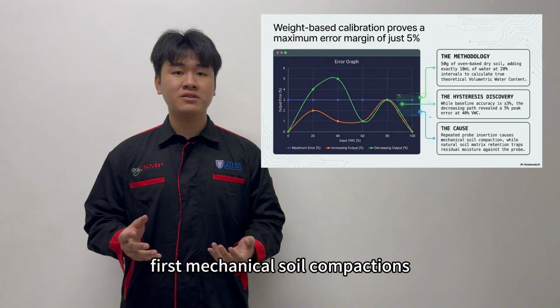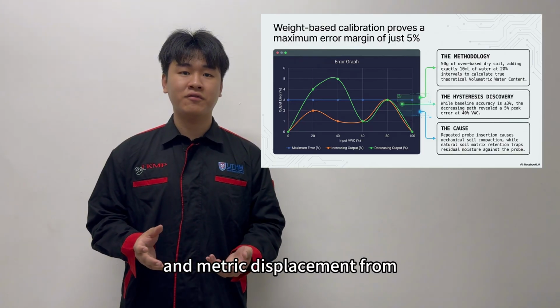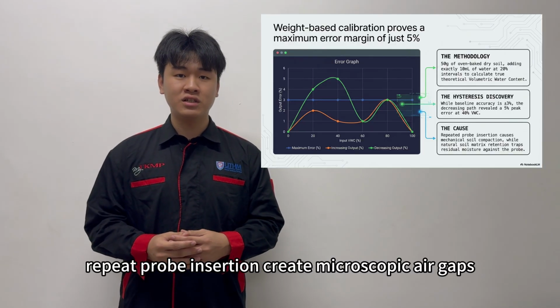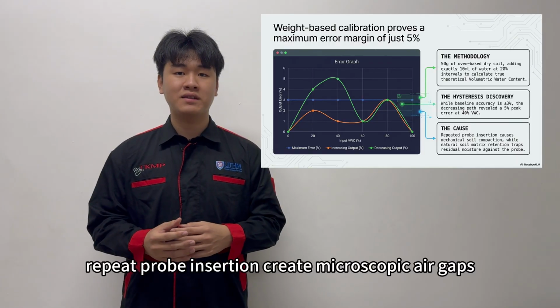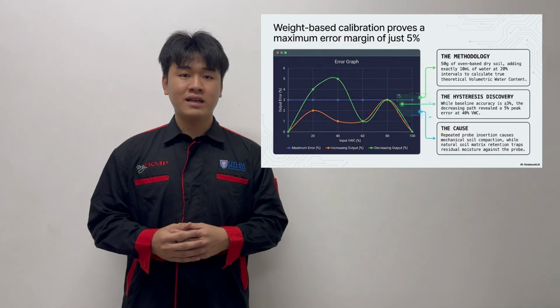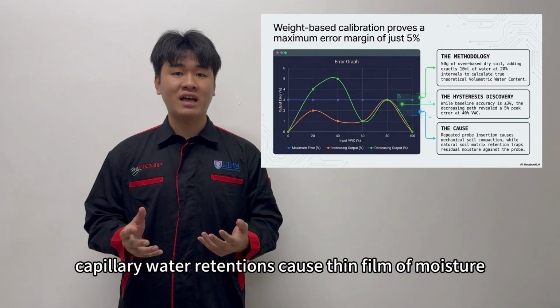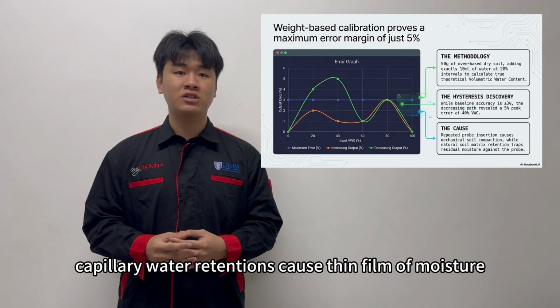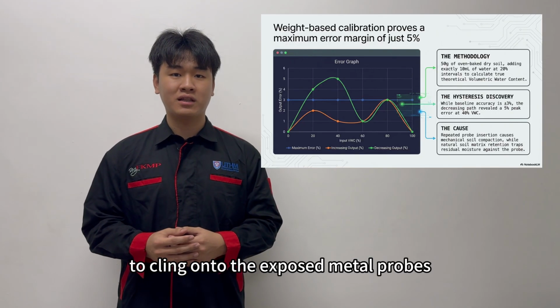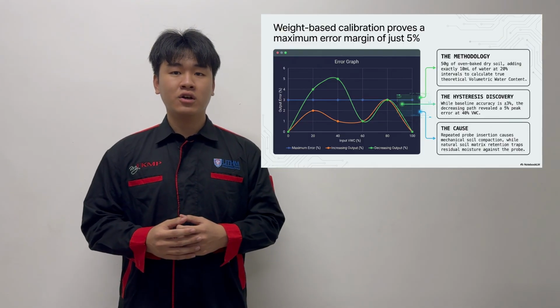First, mechanical soil compaction and matrix displacement from repeated probe insertion create microscopic air gaps around the electrodes. Second, capillary water retention causes a thin film of moisture to cling onto the exposed metal probes during removal, creating a lingering resistance measurement lag.